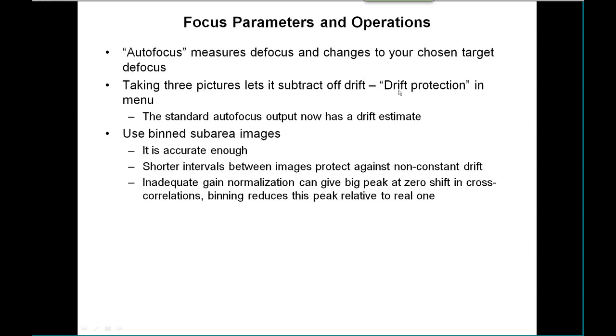Another important point about focusing: the recommendation is to use binned sub-area images, and this is important for several reasons. First, it's accurate enough because there's sub-pixel interpolation in the binning, and you have a several-pixel shift between the images you're measuring anyway. Second, if you have any kind of non-constant drift — such as after tilting — the drift is dying away slowly. You want to take those focus pictures as fast as possible with the shortest intervals between them, and binning along with using sub-areas makes that happen.